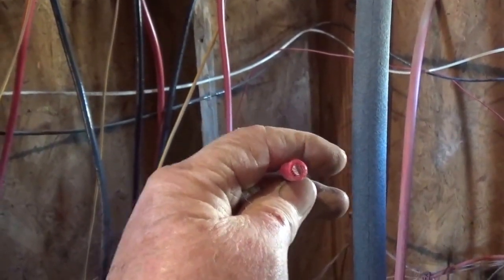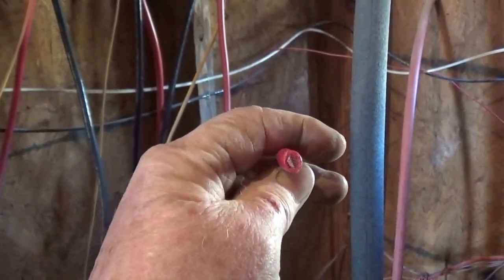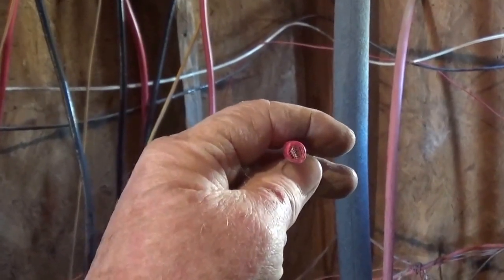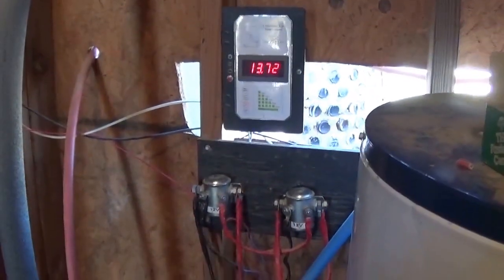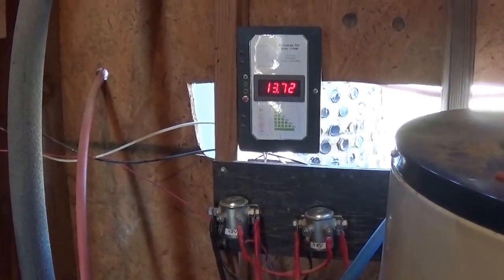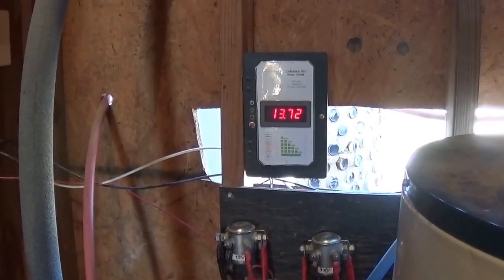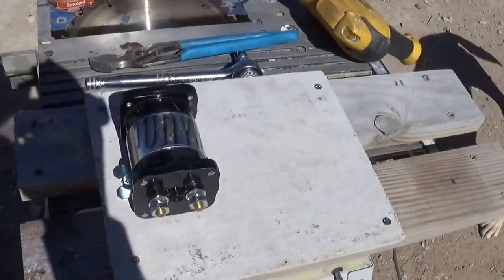What we have to do is put on bigger wire. I'm going to put bigger wire on all the heating elements, and we're going to use this opportunity to go to a new relay from Thermodyne. I mention Thermodyne all the time because I buy products from them due to their great customer service — that certainly doesn't mean there aren't other people out there that make equally good products.